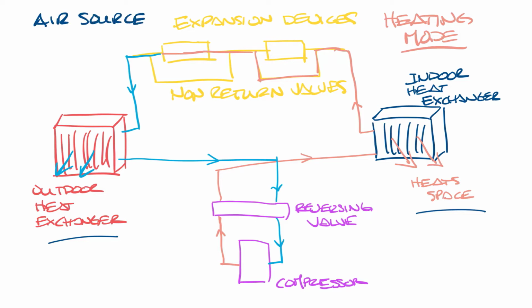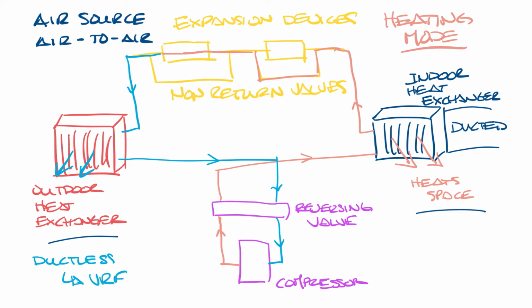Air source heat pumps are also known as air-to-air heat pumps because you're taking heat from the air and transferring it to supply air. Your home air conditioning system is very likely a ducted air-to-air heat pump. As I mentioned in one of the previous videos, the indoor heat exchanger would be ducted to the ducts in your house that supply air to all the spaces. A ductless system could be like a VRF, which I explained a couple weeks ago as well, or a mini-split system. Mini-split heat pumps are primarily seen in smaller residential systems, and unlike VRF, which can provide cooling and heating to the system at the same time, mini-split systems can only provide cooling or heating at any given time.